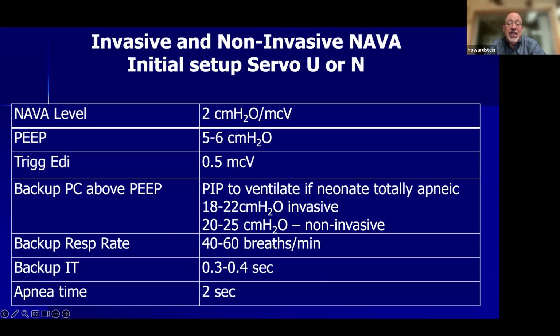Set your rate at physiologic levels like you would on conventional ventilation, and your I time the same way. We start with an apnea time of 2 seconds. If the baby's stable, we leave it alone. If the baby is having spells, we will go shorter on the apnea time in increments all the way down to 1 second.